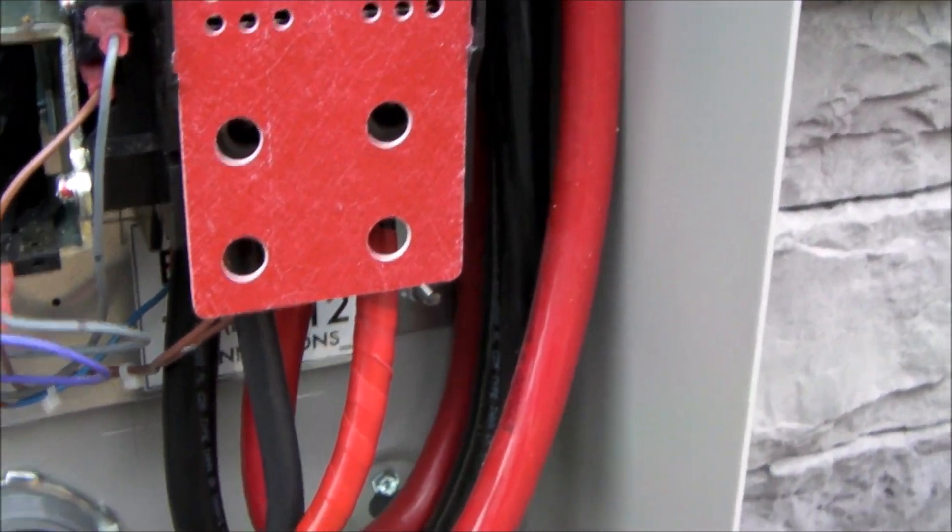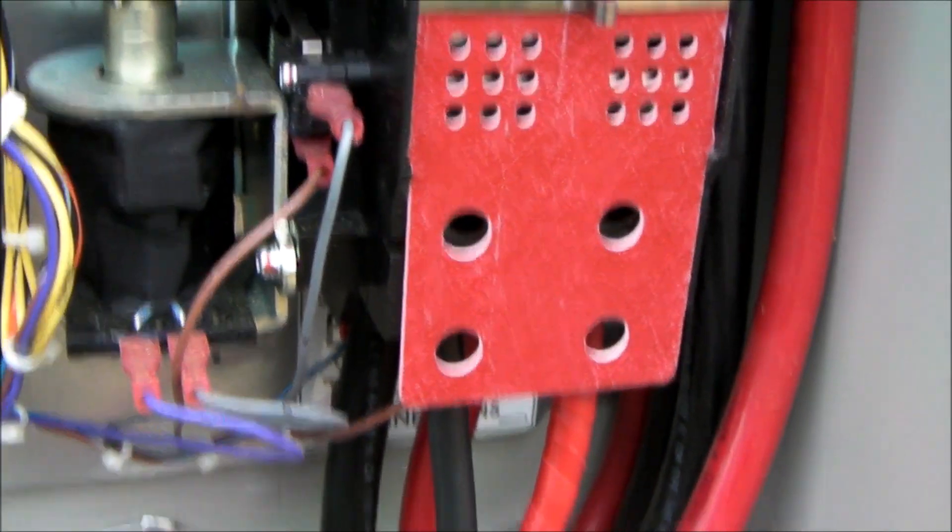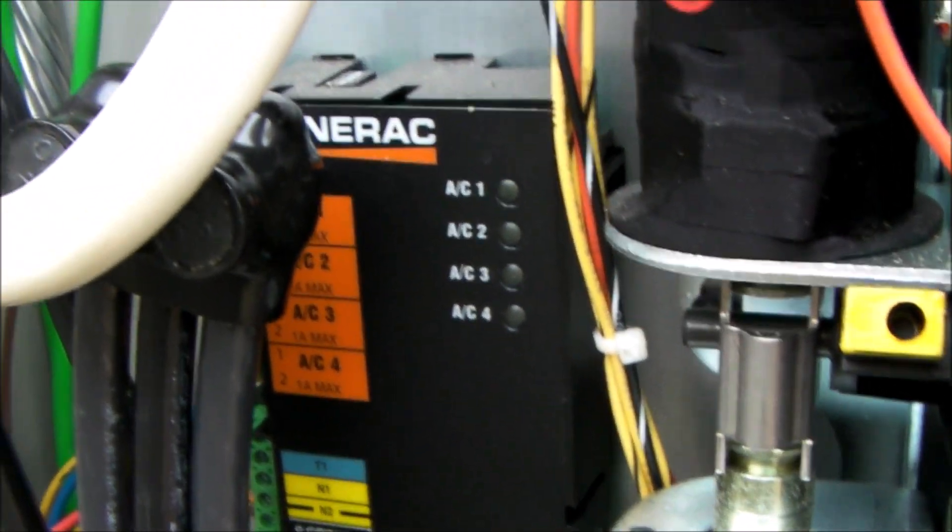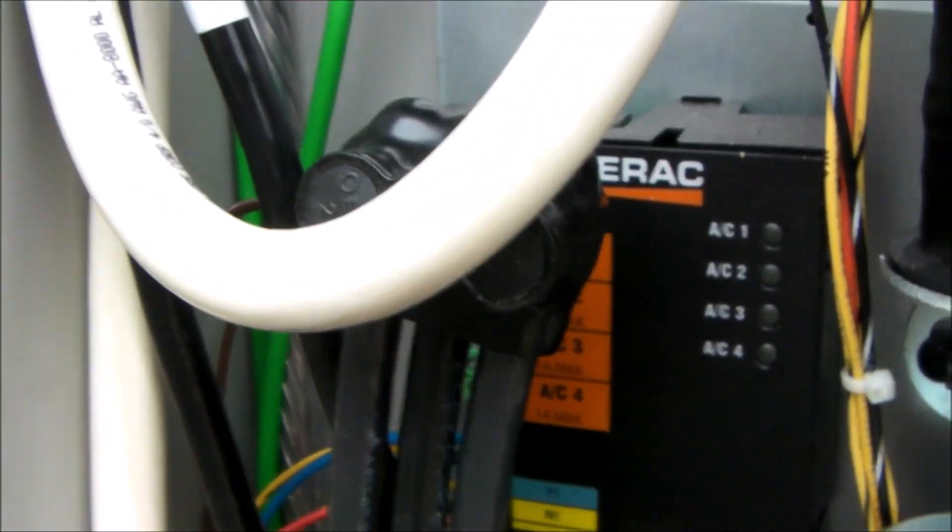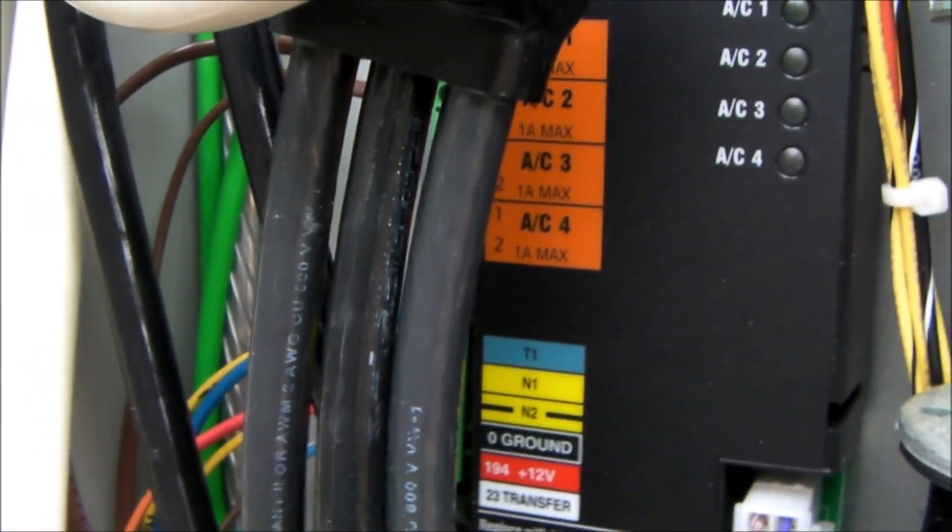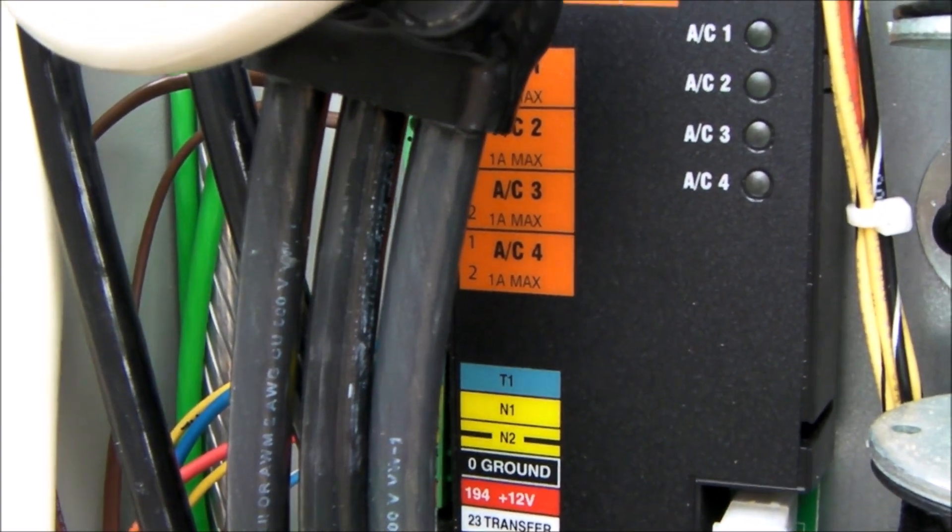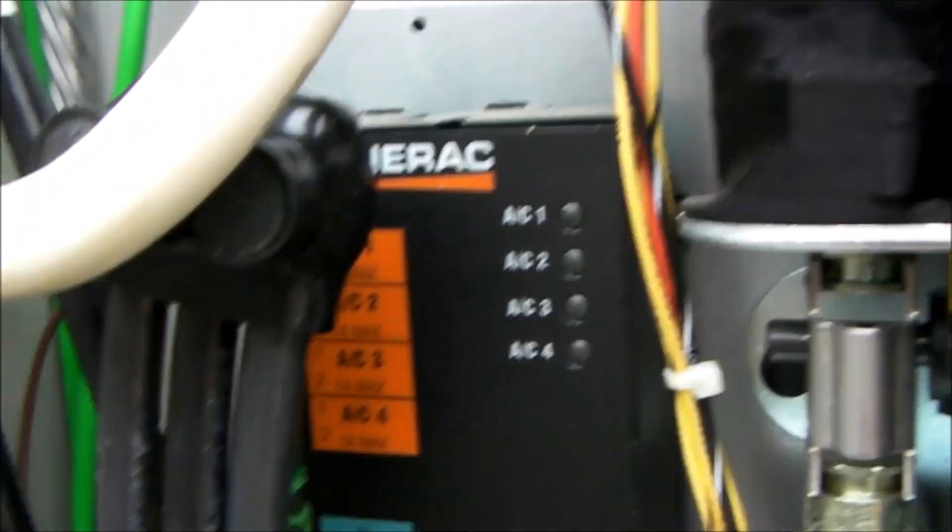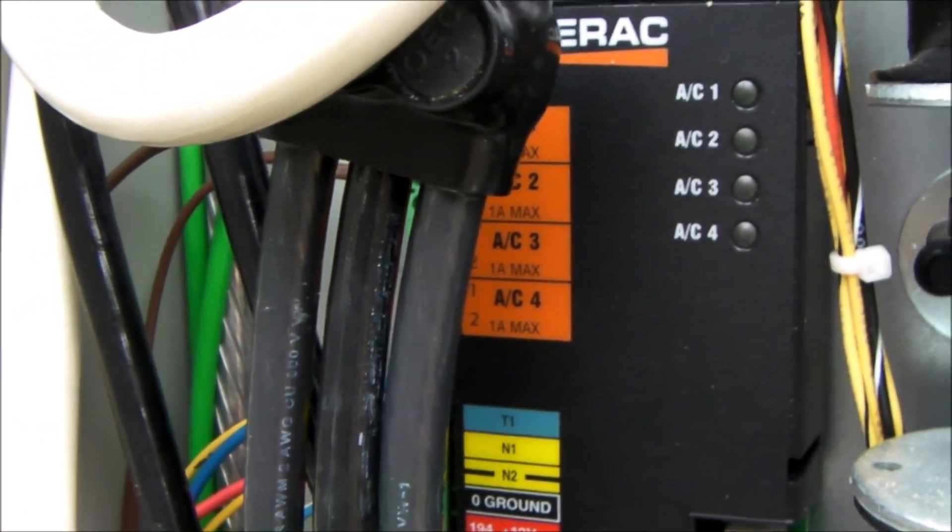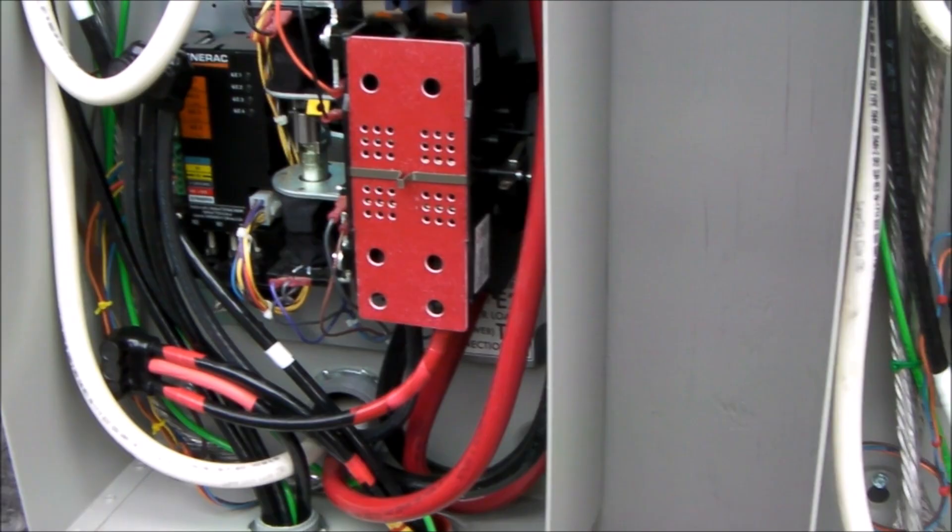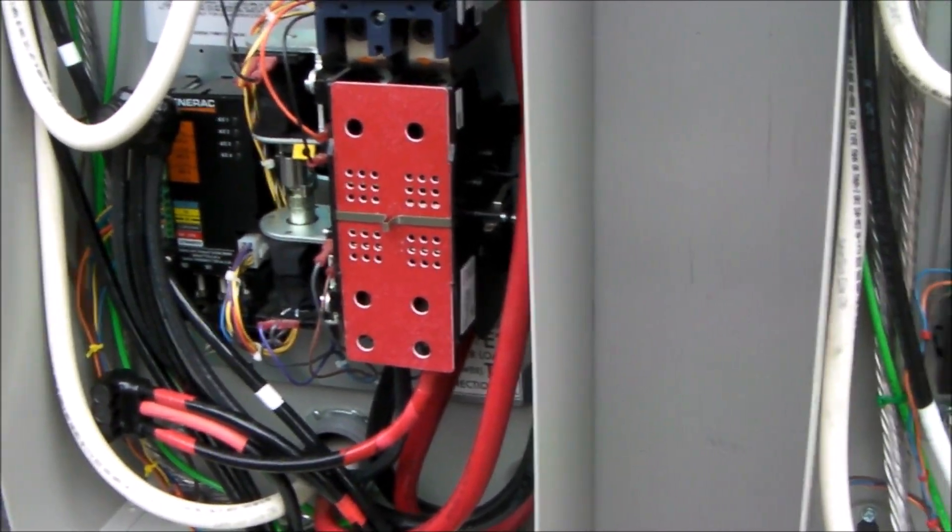Similarly on the black, the black from the other transfer switch comes down, comes through, comes up to this Polaris connector right here—one of those three black leads. The other black lead goes over to this transfer switch, and then I've got the center of the Polaris coming down and going back to the generator. So those are your only connections that you really need to make. It's not all that complicated.